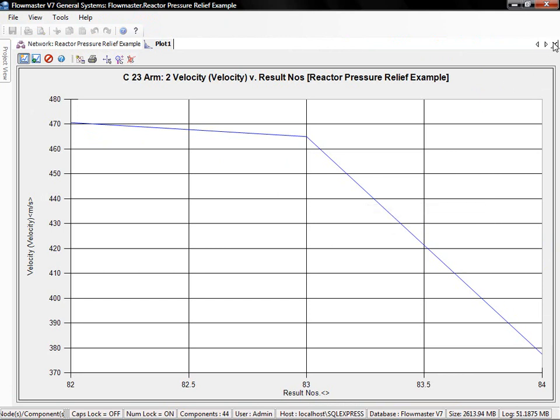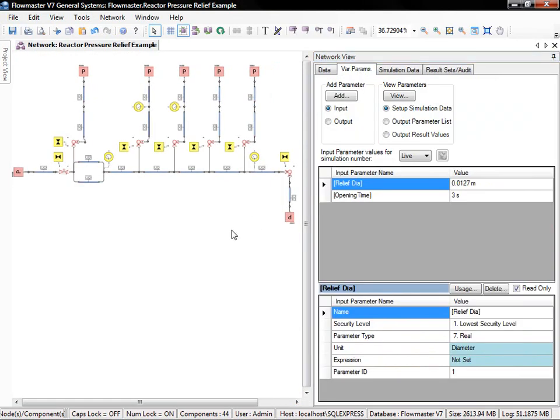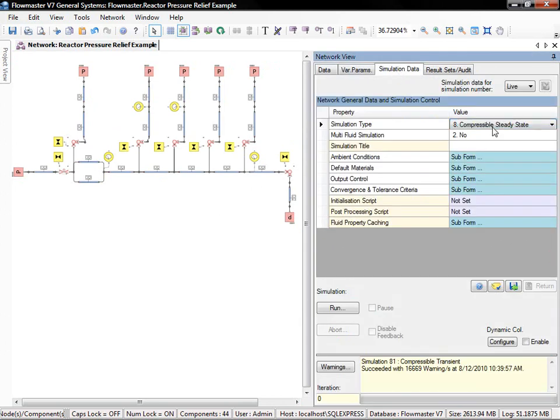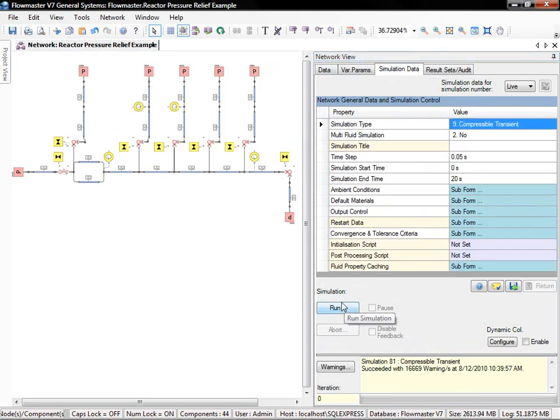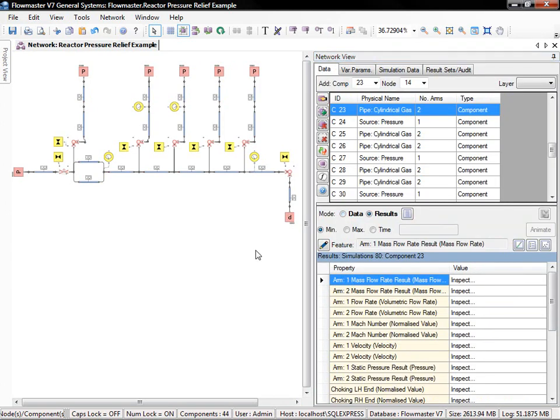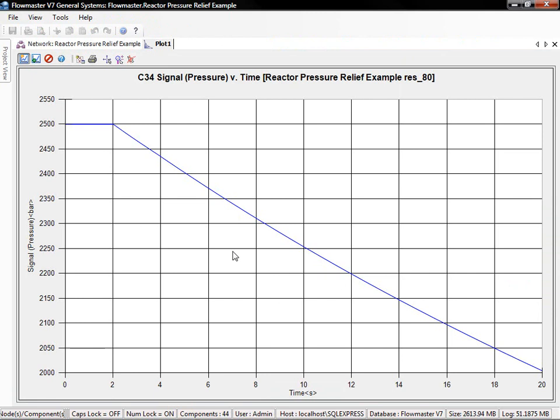Once we have that, we are also going to want to look at the transient behaviors of the system. So if we go ahead and we pick, let's say, the 3 different sizes, again 1/2 inch, 1 inch, and 2 inch, and we can run a transient analysis for each of them, and we're going to run for about 20 seconds. And again, what we were looking to do is bring the pressure down to 1500 bar inside of the reactor, where we know that the reaction will be stopped.